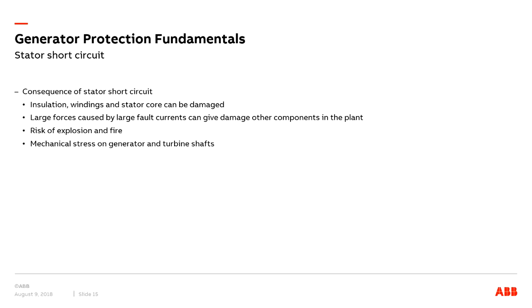So short circuits in the generator will cause large fault currents. And these fault currents will result in large forces that will create mechanical stress to other components in the power plant. There are risks of fire and explosion in connection to the short circuits in the generator, as there is inflammable material in and close to the generator. And the short circuit itself will result in torsion variations causing mechanical stress on generator and turbine shafts. So short circuit can cause both electrical and mechanical problems in the generator.